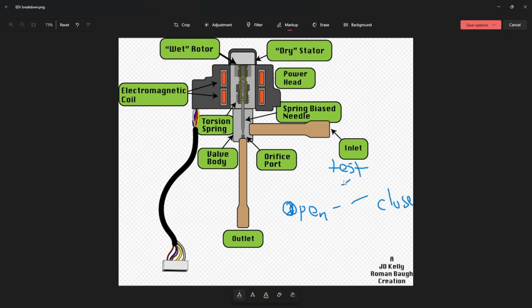So if you short the open to test pin, that's going to be doing an open test where it will drive your stepper motor full open and keep it in that position for about 5 minutes. After that 5-minute timer, it will drive it full closed, then resume normal operation. A close test, same thing. You short the test to close pin for about, I think you only have to short it for about 10 seconds. But when you short those pins together, it'll drive the valve full closed and keep it full closed until either the low pressure switch trips or 5 minutes, whichever comes first. So those are some ways you can test the valve to make sure the stepper motor is driving open or closed the way it's supposed to.